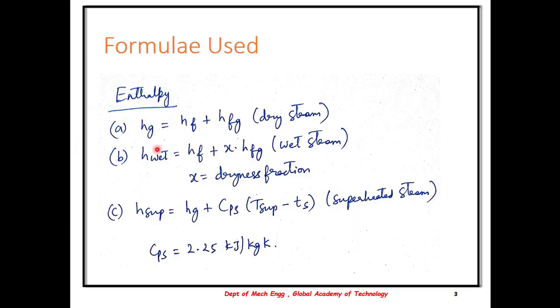The formulas listed are as below. HG is the total enthalpy content. For dry steam, it is HF plus HFG. Whereas for wet steam, the formula changes to HF plus X into HFG, where X is the dryness fraction. In case of dry steam, the value of X is taken as 1.